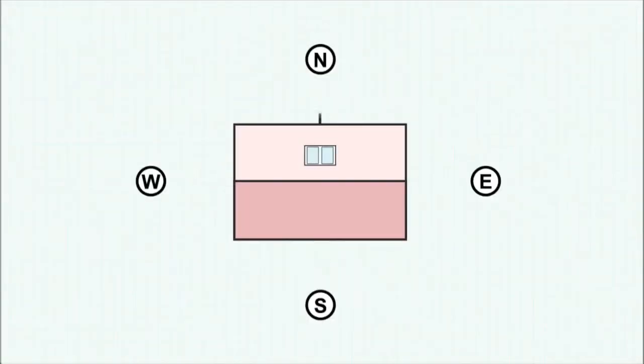Collectors should ideally face true north in a shade free position. Facing the collectors 45 degrees from the north will result in only minor reductions in performance.